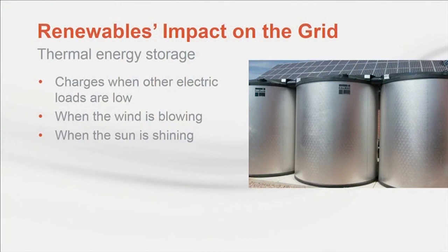Thermal storage, compressed air storage, and batteries can be charged with excess wind at night or excess solar during the day, which helps the utilization of renewable assets. While we normally think of cold thermal energy storage as something that happens strictly at night, this doesn't have to be the case, especially as times of oversupply and cheap energy can happen during the day. The system charges when other electric loads are low. This could be when the wind is blowing at night or over the weekend when many commercial buildings are less active.